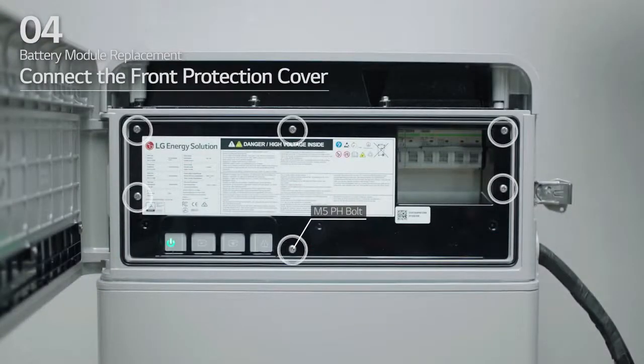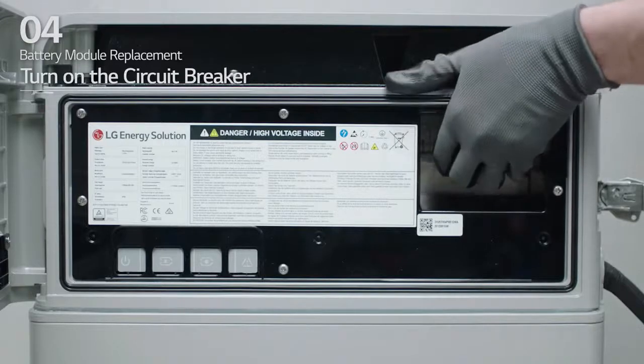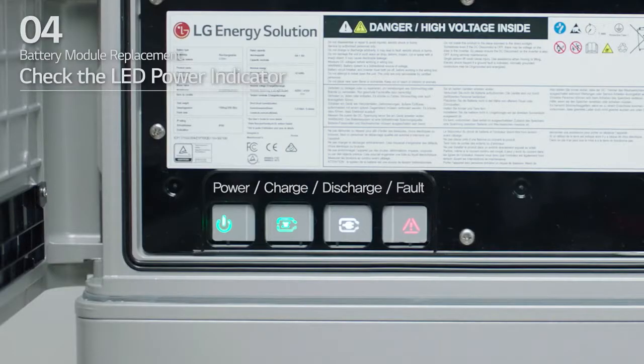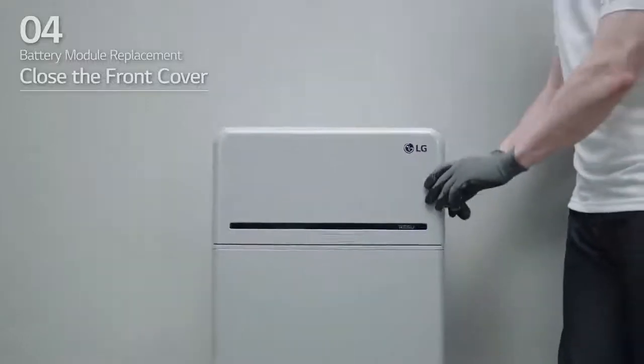Connect the front protection cover using six M5 PH bolts. Turn on the circuit breaker. Seconds after the circuit breaker is switched on, four LED indicators will light up. To ensure that installation has been done correctly, check that the LED power indicator is green. Finally, close the front cover and turn on the inverter.